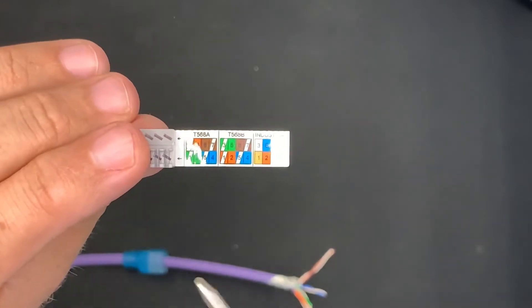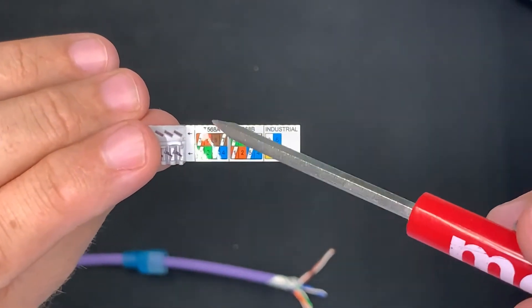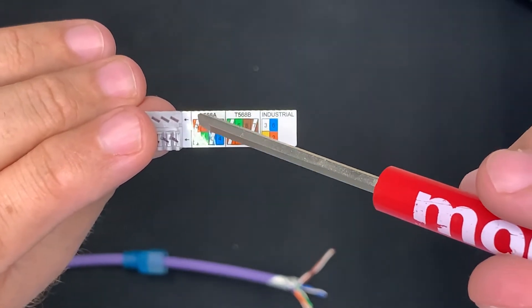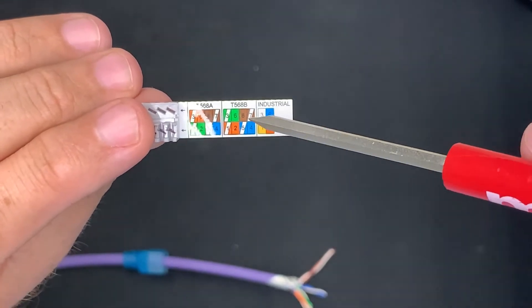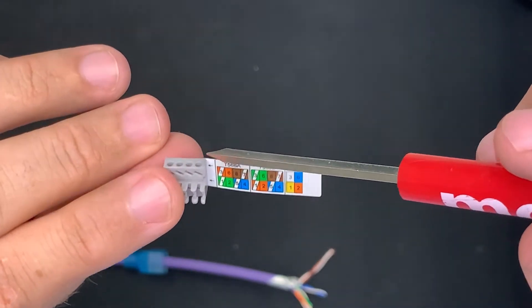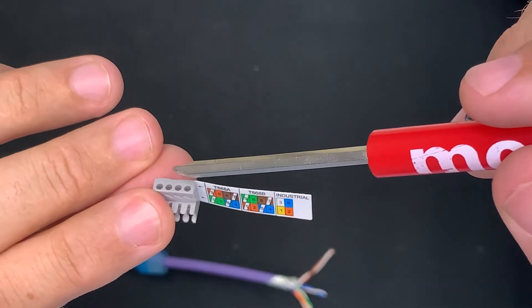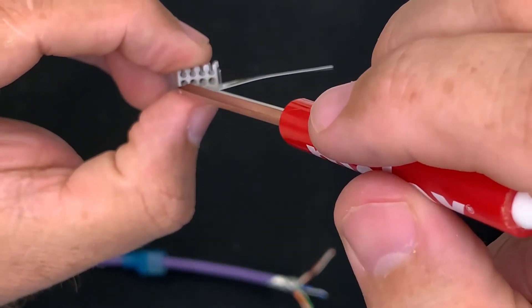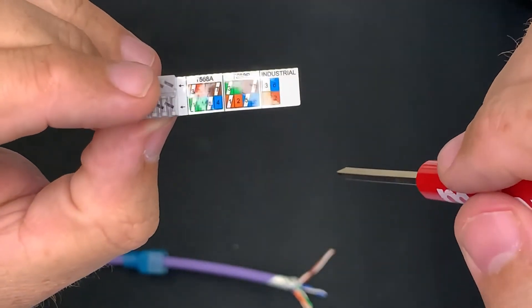Now, if you look at the wiring cap, you will see on the color schematic that there is an arrow in the front and an arrow in the back. We are going to use B-spec. This arrow in front means the cable must be on the bottom coming out in the front. So, you will slide it from the back on the bottom. You will slide your cables through.